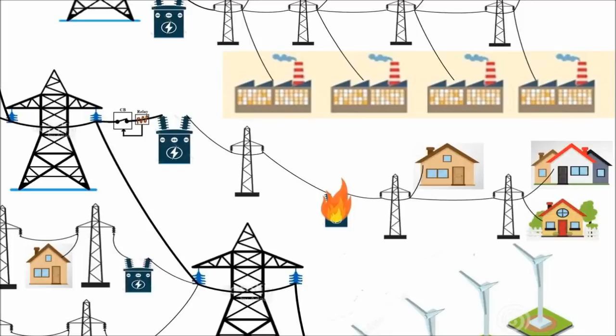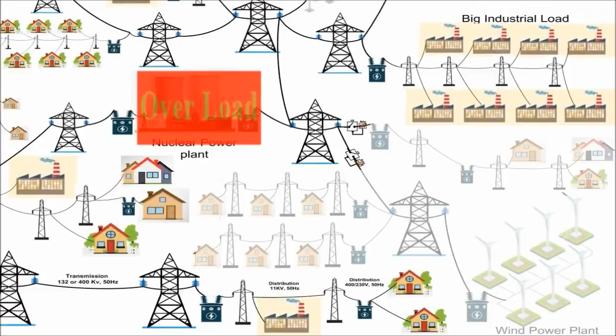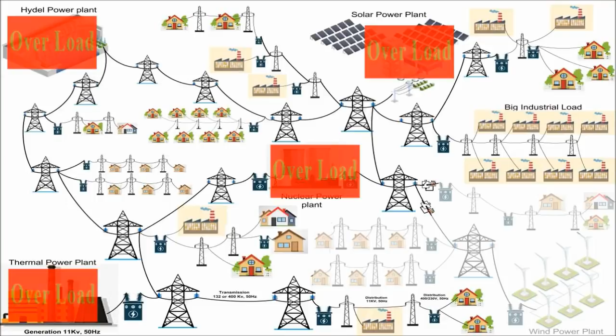But sometimes these relays can make false triggering. That is, without any reason, it may isolate a big part of the system. Unfortunately, if at that instant there is a high electricity demand on the system, this increases the possibility of blackout, that is, failure of units one by one and complete shutdown. Many times, failure of a big transmission line causes blackout in a big part of the system. Natural disasters like earthquakes and storms are usually the main reason for various historical grid failures. So these are some basic reasons and this is how grid failure occurs.